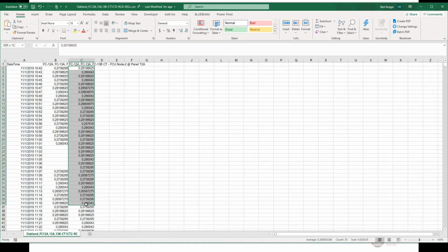We'd be adding up power, and we'd be assuming each one of these readings was agnostic of time. And so it becomes more challenging if we say, I have this fan coil I want to know the energy on, and then I have another set of data, let's say other fan coils, that I also want to add the energy up for, and the time step is maybe every 15 minutes.